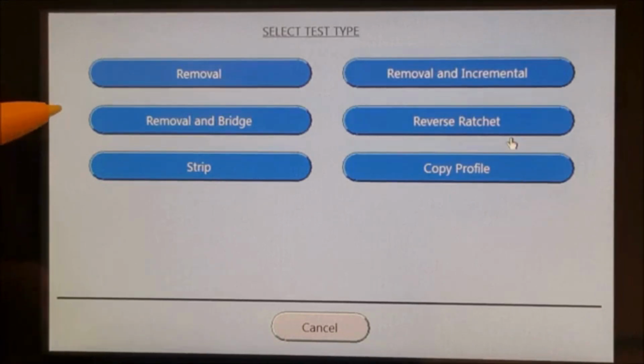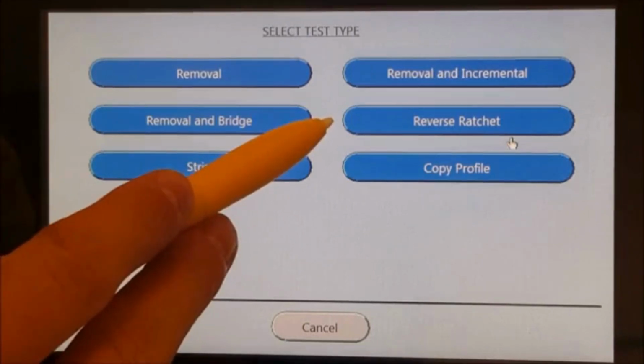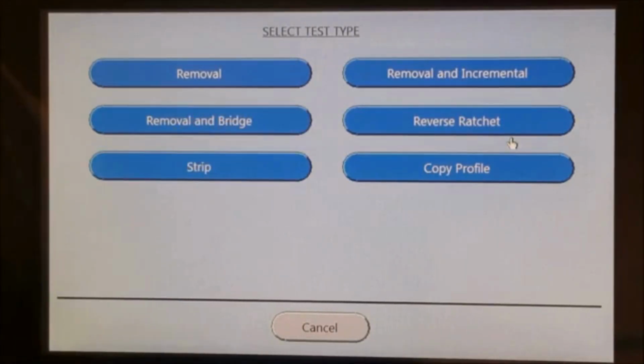The Removal and Bridge test determines the rotational force needed to remove a cap and break the bridges that join the cap to the tamper-evident band on plastic and aluminum caps. The reverse ratchet test measures the torque required to rotate a child-resistant type cap without engaging the child-resistant mechanism. This means that there is no vertical downforce. The strip test is designed to measure the torque required to strip the threads of any cap.